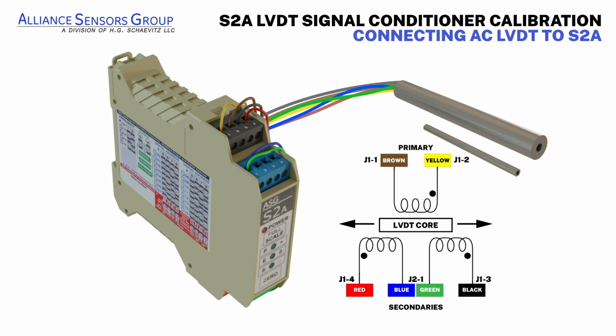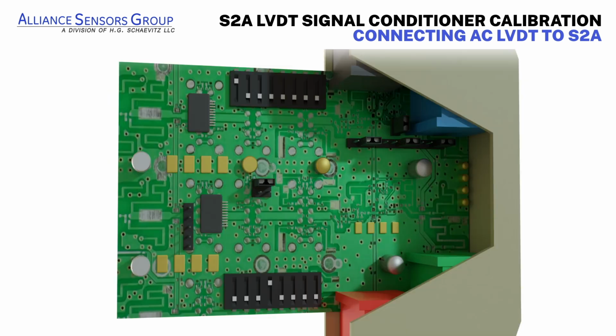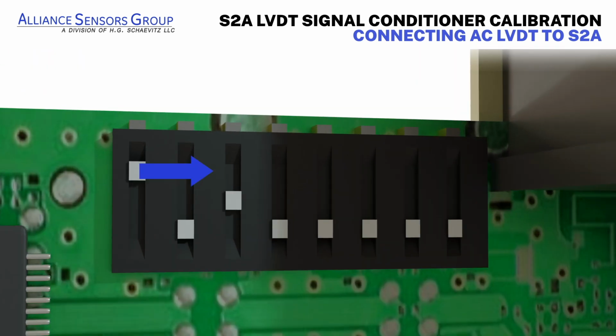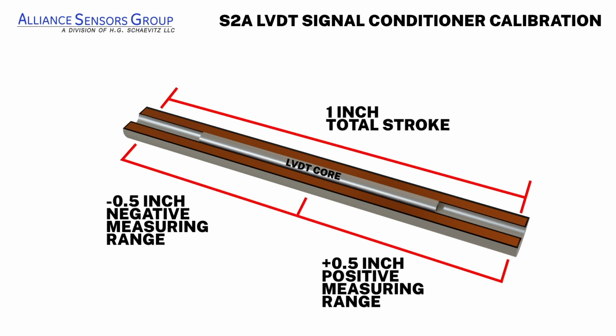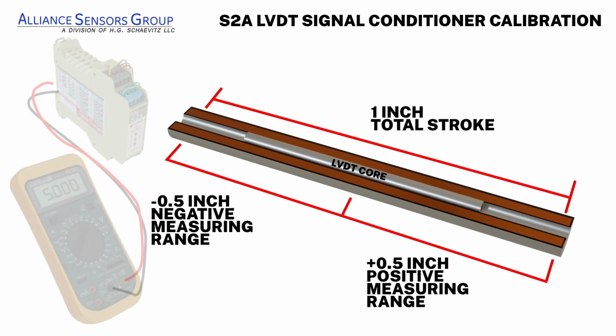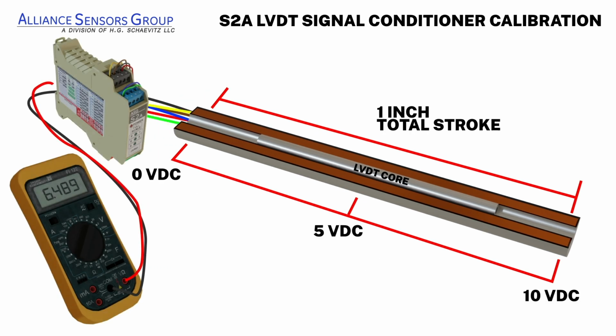If the connections give you the wrong directional sense of output, interchange the 2 primary connections or flip DS23 on the S2A signal conditioner's PC board to on. For this demonstration, we'll be using an LVDT with a plus and minus 0.5 inch measuring range, which the S2A recognizes as a total measuring range of 1 inch, along with the S2A's default analog output of 0 to 10 volts DC set with DS14 turned on.